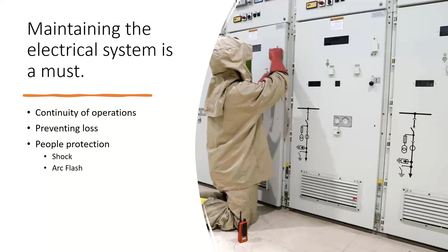And if the breaker's not operating up to the way it was designed to be, if it's dirty, hadn't been operated in a while, even a small amount of it, okay, now it takes 20 milliseconds instead of 16. That would make a huge difference on your arc flash calculation.